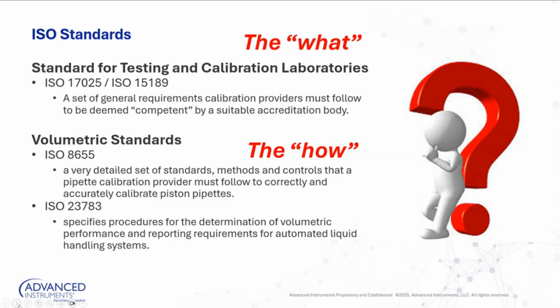Around the volumetric standards, specifically for pipettes, it's ISO 8655. That is a very detailed set of standards and methods that pipette calibration providers must follow to correctly and accurately calibrate a piston pipette. And more so around automated liquid handling, it's ISO 23783, which is the procedure for volumetric performance to meet the requirements of the standard for automated liquid handling systems. So once again, 17025 and 15189 are the what, and the how do I actually do this is 8655 and 23783. If you take away nothing from this presentation, I want you to remember those two specific things, because oftentimes people will say I follow ISO 17025 or ISO 15189. That's just the what. How do I actually do this? The granularity is in ISO 8655 and ISO 23783 when it comes to automated liquid handling.